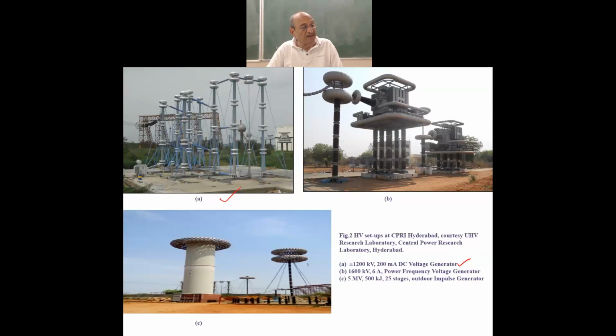So as you can see here, this appears to be in 2 stages. 800 kV each has been designed, if I'm not mistaken. Yeah, in 2 stages. The 800 kV each is giving you 1600 kV AC power frequency, 6 ampere. 6 ampere is when it can test objects requiring very high magnitude of current. There will be power cables and transformers, as you know. And 1600 kV is good enough for any research work for 1200 kV rated voltage.